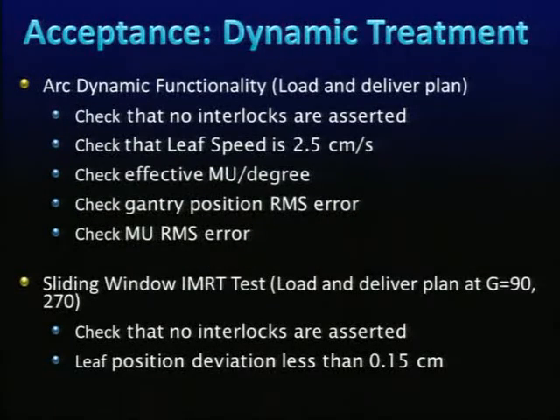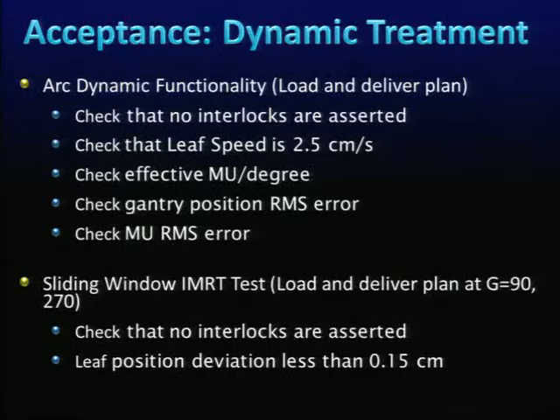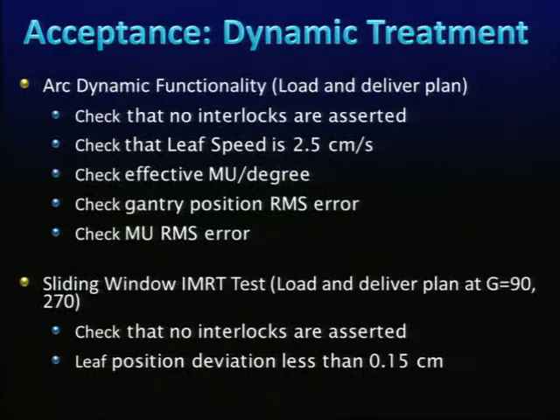Before commissioning begins, the manufacturer provides an acceptance test. For dynamic treatment, one example of acceptance testing for arc dynamic functionality includes checking interlocks, leaf speed, effective MU per degree, gantry position, and MU errors. For sliding window IMRT, they verify interlocks and MLC position accuracy within 0.15 cm.